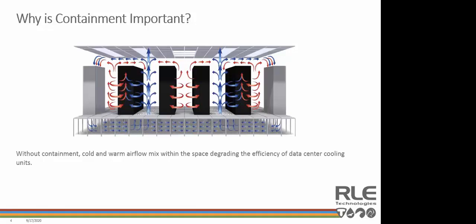Well, we hope to answer that question for you as we move through this webinar. The image on this slide illustrates what tends to happen when cold and warm air mix in an uncontained raised floor data center space. Cold air is supplied in an underfloor plenum and delivered through perforated panels in cold aisles, and warm air is returned to the cooling units to be reconditioned. Without containment, cold air can mix with warm air during the return to the cooling units, and warm air can recirculate into the cold aisles, increasing temperature of the cold air supply.